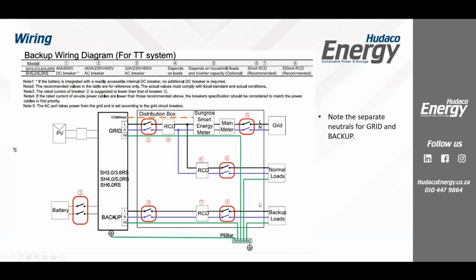Okay, so some key points, please. Separate neutrals, okay, for grid and for backup. So make sure that your loads are on separate neutrals. We've had a few cases where people have taken devices and moved them from normal loads to backup loads or vice versa, and they've forgotten to swap the neutral along with it as well. And then it can cause an issue. So please just make sure that you keep the neutral separate. Please make sure that the PV panels and the batteries are also earthed. Earth those to the chassis, and then that's straight to your earth spike. You can do that on the chassis, or I suppose you could actually do it in the DB as well.